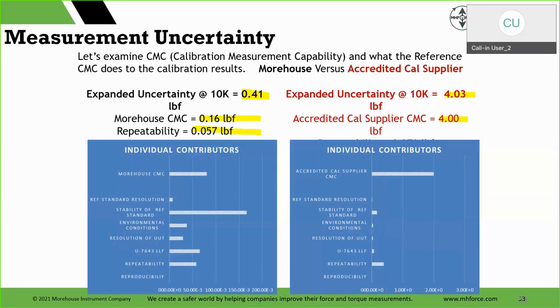If you're going to have your references calibrated by somebody, or you're going to put those references in another machine to do calibration, where do you want to send them? This all points back to starting with primary standards. Expanded uncertainty when calibrated with primary standards is approximately 10 times lower than using secondary standards. If you're making force measurements, primary standard calibration might be a must.